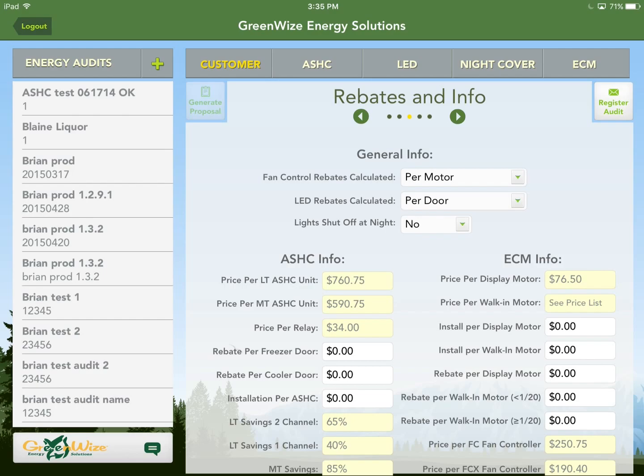For prescriptive rebates, you'll see the amount right on the rebate application. Fan controls can be per controller or per motor — check the application. LEDs are calculated per foot or per door. Most rebate providers now have most equipment as prescriptive since they've been doing it long enough. The 'Lights Shut Off at Night' field is for refrigerated case or freezer door lights. Many stores shut those off at night since nobody is in the store, so this will often be Yes.